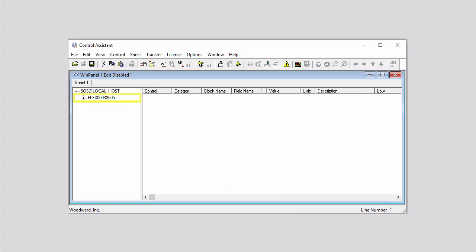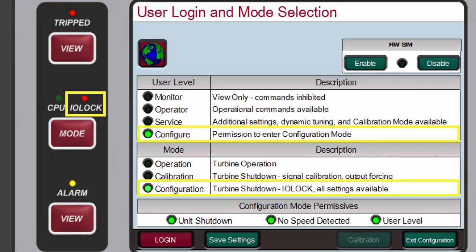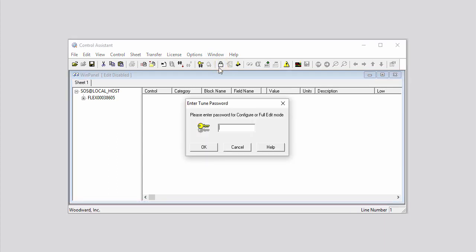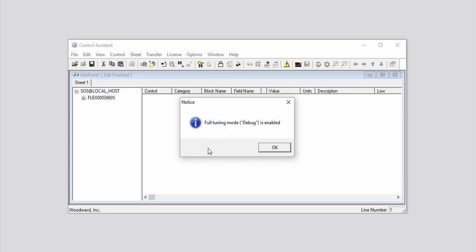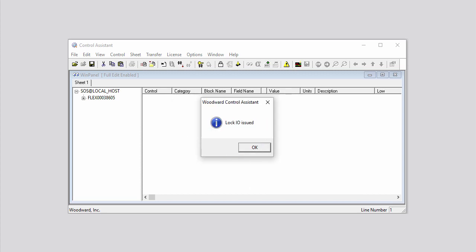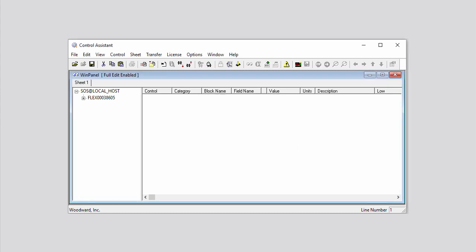The name of your controller is in the left panel. To send or receive tunable files, your controller must be in Input Output Lock. To put it into IO Lock, you can either log in to Configuration Mode on your controller, or issue it from Control Assistant. To issue it from Control Assistant, click the Lock icon on the toolbar. In the Enter Password window that opens, enter 1112, then click OK. In the Notice window that pops up, click OK to indicate that you understand that Full Tuning Mode has been enabled. A Woodward Control Assistant window pops up — click Yes to indicate that you want to continue. In the next Woodward Control Assistant window that pops up, click OK to indicate that you understand that the controller is now in IO Lock.